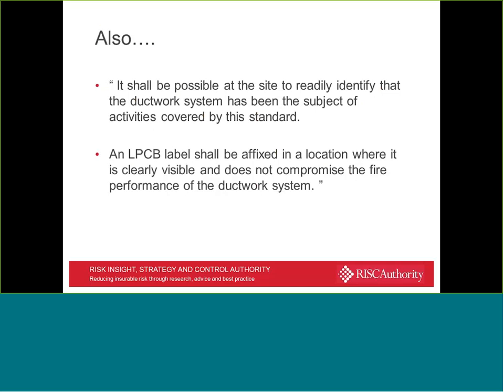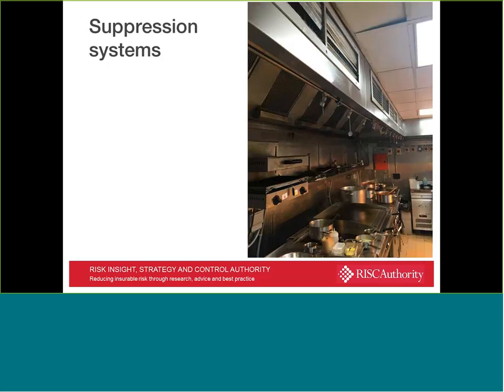The standard also goes on to say it needs to be possible at the site to readily identify that the ductwork system has been the subject of activities covered by this standard, and requires a label to be affixed in a location where it can be clearly visible and doesn't compromise the fire performance of the ductwork system. So not only should we know that it's being cleaned effectively, not only should there be a report that proves that and describes any problems that there may have been in the cleaning process, but there should also be a label there that enables us to quickly identify the fact that the system has been cleaned.